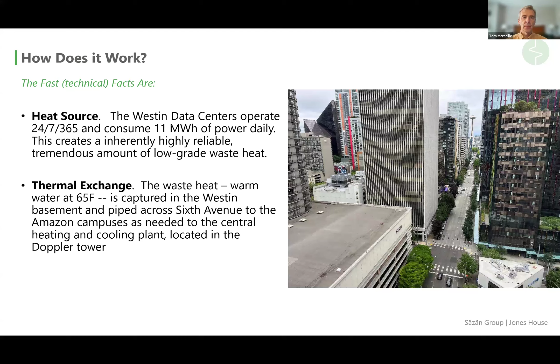So that's low-grade waste heat, which is what you can typically capture easily. That waste heat can be used a lot of different ways. We sometimes call it an ambient loop in the district energy world, or a condensing water loop. They're using it to cool - that water is cooling the data center, typically going up to cooling towers on the roof. In this case it doesn't have to, because it's coming across the street to Amazon.